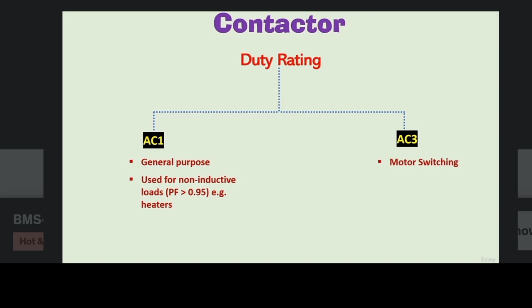AC3 contactors are used for switching of squirrel cage motors as they draw high inrush current during starting, which is up to 5 to 6 times more than the nominal current of the motor. AC3 contactors are designed to withstand that high inrush current. They are used for motors for fans, elevators and pumps. So inside the MCC panels of your air handling units, you will find these AC3 rated contactors.